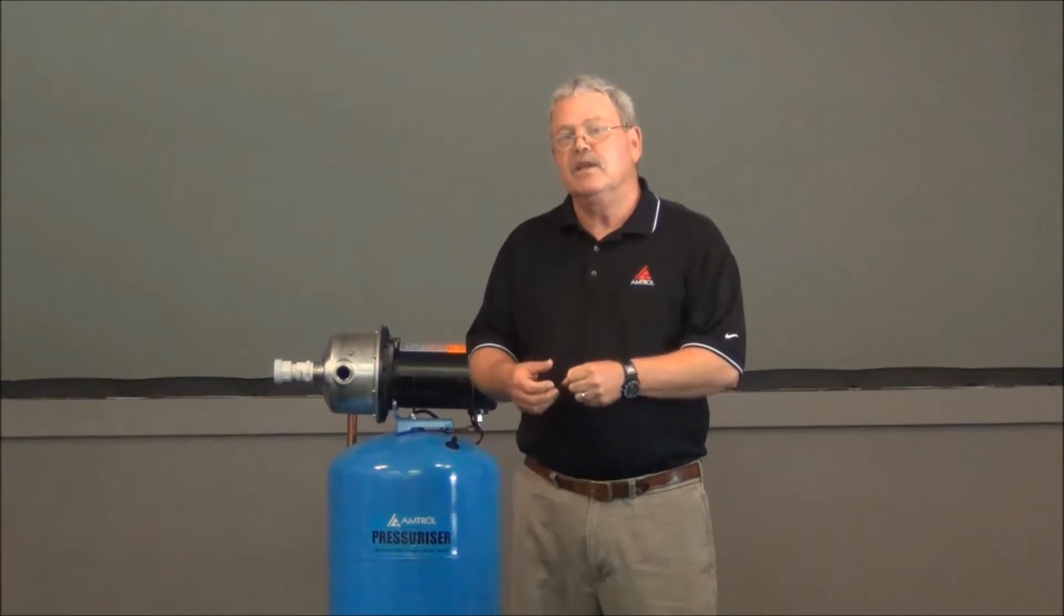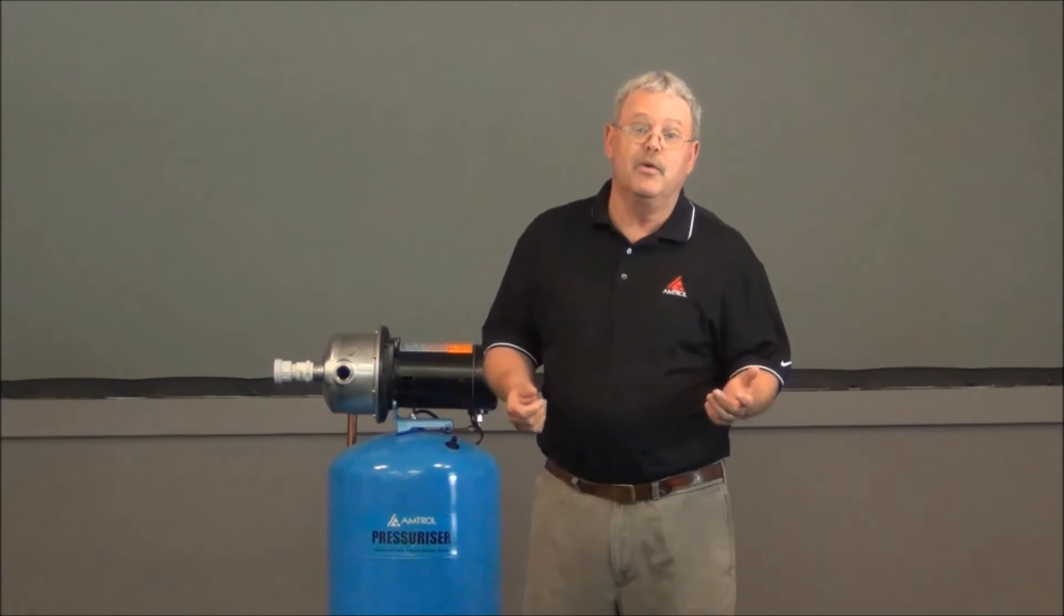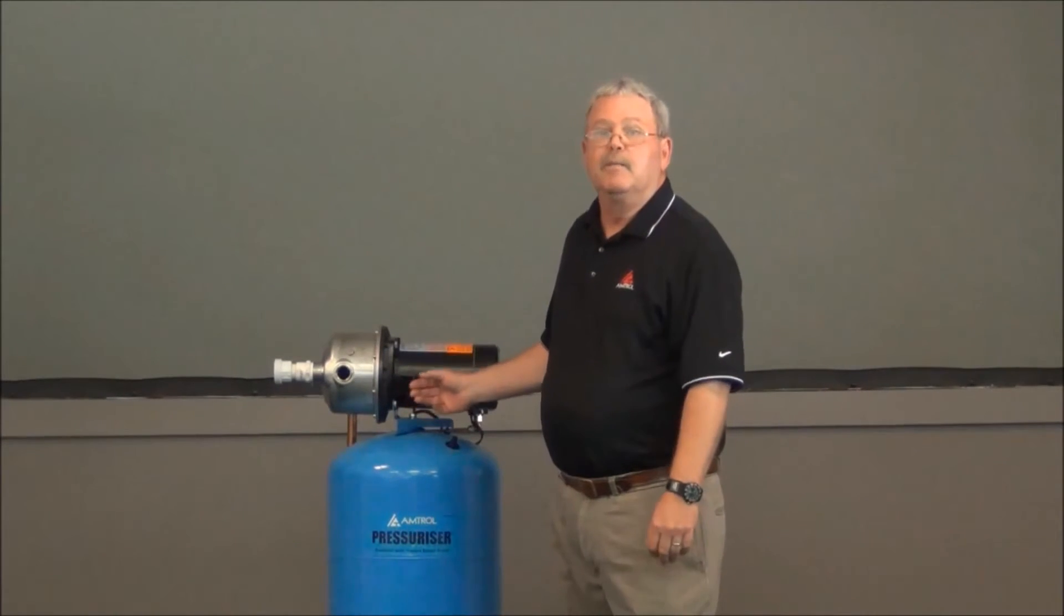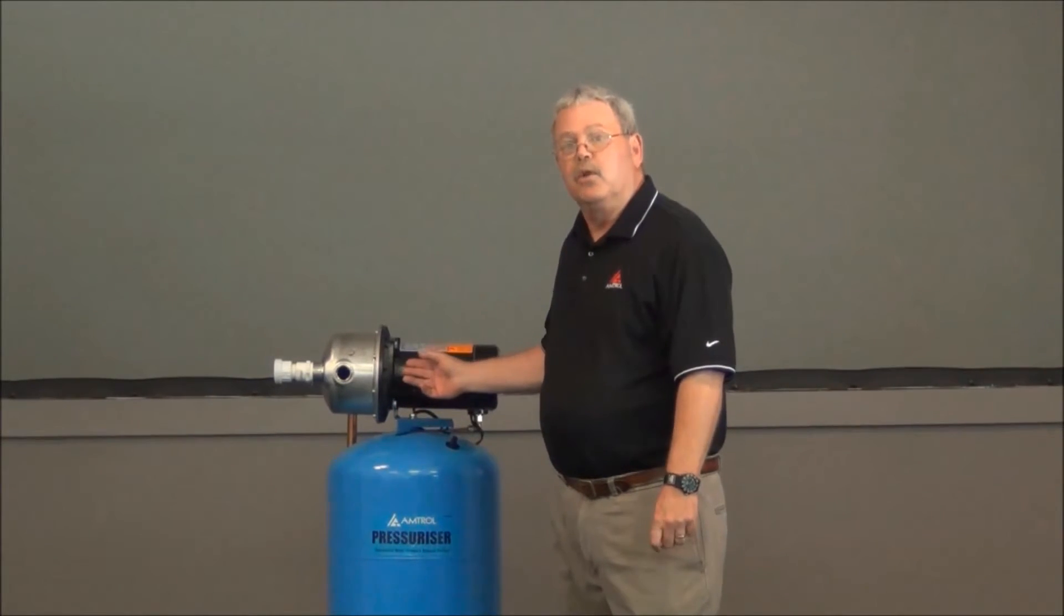...what happens is we start to get a little arcing in there and you run into a voltage situation that way too. And you start getting low volts to the motor. Again, if we get low volts to the motor, what happens is we run into thermal overload, the pump will cut off on thermal overload.